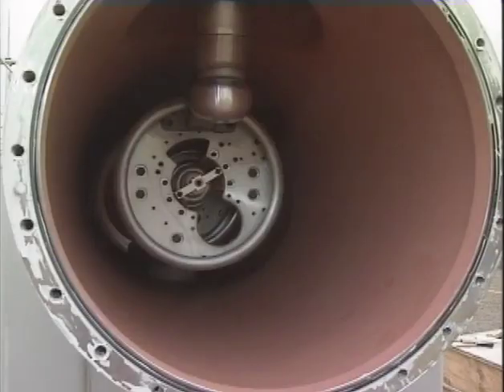After all decomposition products and contaminated materials are removed from the area, the equipment is ventilated to disperse any lingering gas before any additional servicing is performed. In most cases, normal maintenance or access to gas-insulated equipment involves the general procedures that we just looked at. It's very seldom that you'll need to work on gas-insulated equipment that has experienced an internal fault, and even more rare that a pressure relief device or the equipment itself ruptures as a result of an internal fault. But it's best to be prepared and know how to respond in case such a failure occurs.